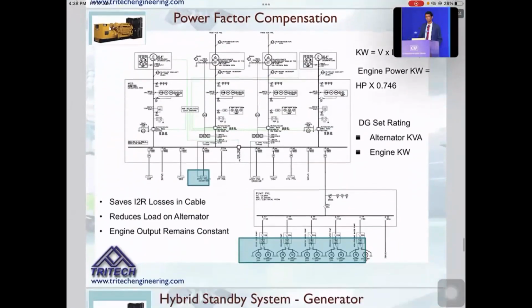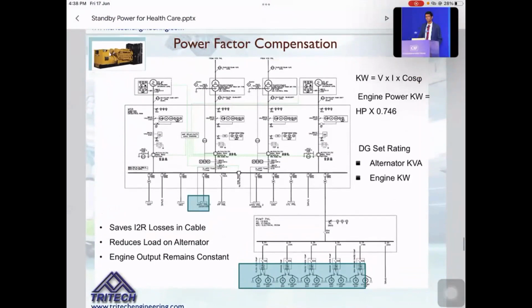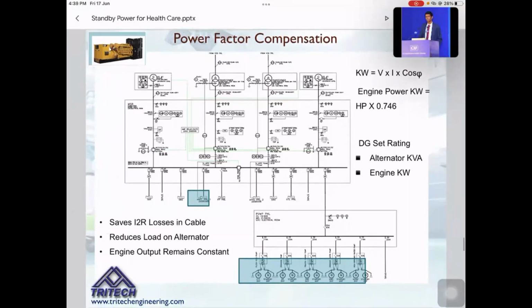Another aspect regarding the generators is the power factor compensation part. Power factor is a utility driven parameter. If you consume power at a reduced power factor, the utilities will penalize you, or you have to pay a low power factor fine. To avoid that, we generally give automatic power factor controllers, which are required at the main panel only. But what happens when the generators are running? The common thought is that you don't need to compensate the power factor for the large loads. Actually, it's the other way around.